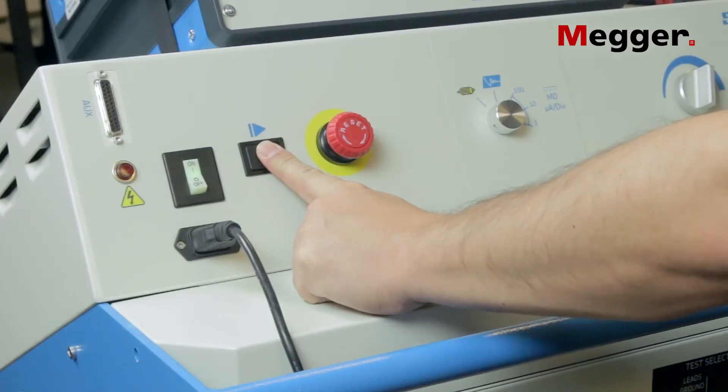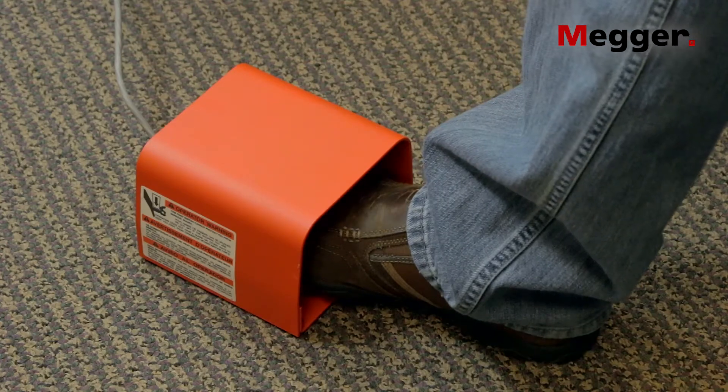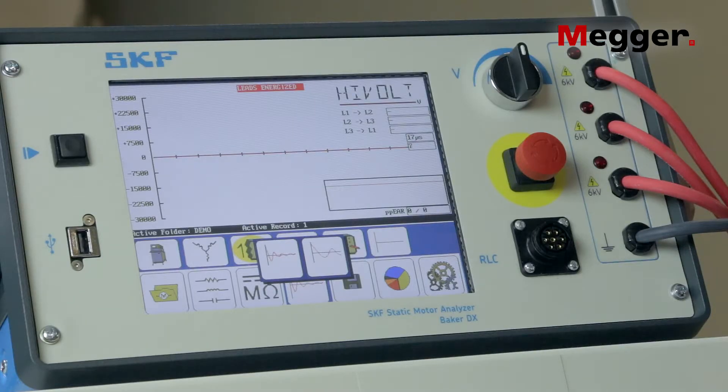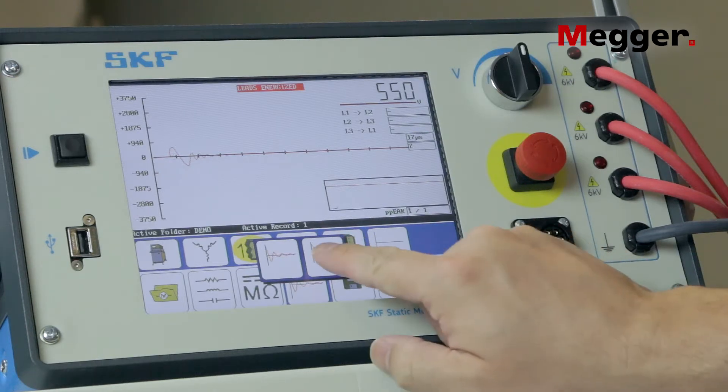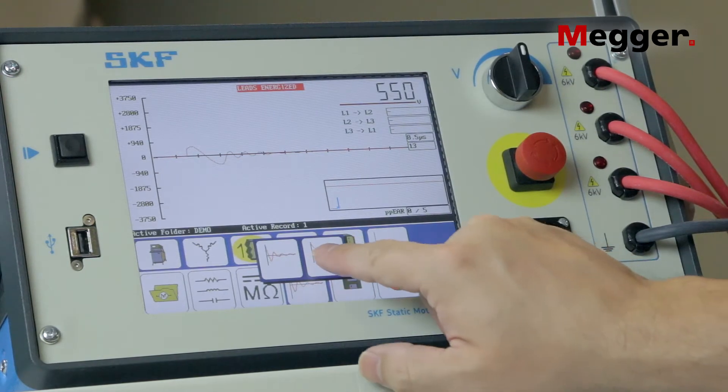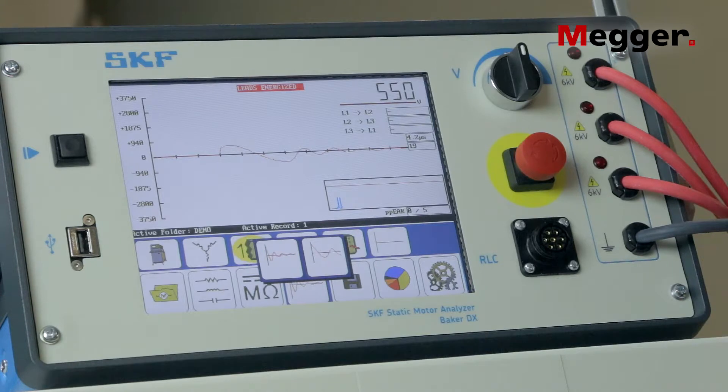Press and hold the push-to-test button or foot switch if connected. Slowly increase the voltage knob until the surge wave can be seen and then adjust the horizontal scale so that the waveform is shown across most or all of the screen. Slowly and continuously raise the voltage to the desired test value. In this case, 14,000 volts. Turning the knob smoothly minimizes the effects of ramping on the pulse-to-pulse EAR.